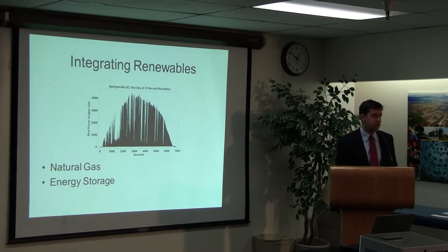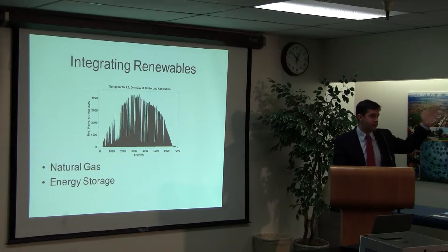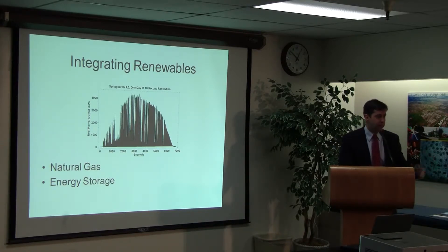As we move toward more decentralized energy generation, we may need more on-site, community-centered energy storage that neighborhoods are sharing. There are other technologies beyond batteries — pumped hydro is a mature technology. Pumped hydro means moving water at different elevation ranges. How many people have driven by Pyramid Lake on I-5? That's a pumped hydro system — two reservoirs at different elevations. At night when energy is cheap, they pump water uphill, then release it downhill during the middle of the day. It's called arbitrage because even though you lose some energy pumping uphill, you end up making money.